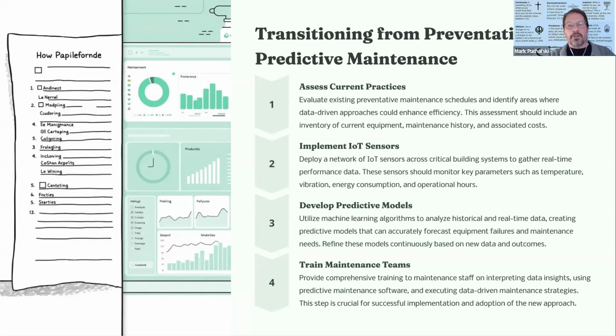And I'm going to change those filters because that's what it tells me to do. Whether I know those filters need changing or not, my work order says to change those filters. So that's what I'm going to do. However, sometimes those filters need to be changed less frequently. Sometimes they need to be changed more frequently. So how do we measure that? Well, a control system can tell us how to measure that, right? And that's where we started getting into predictive maintenance.